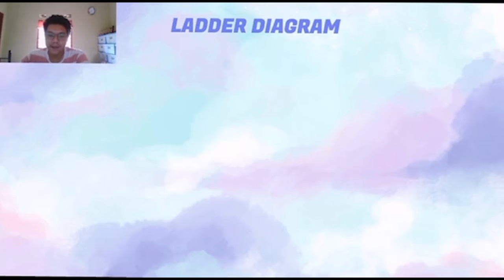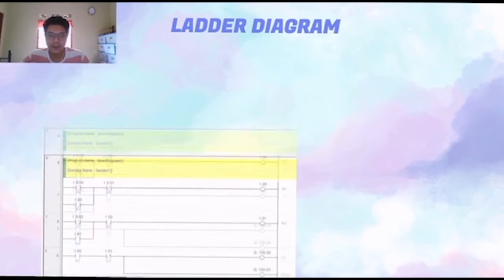Ladder diagram: commonly used to document industrial control logic systems, called ladder because they resemble a ladder with two vertical bus bars for power supply, left and right. The left side is 24 volts and the right side is 0 volts, with as many rungs, or horizontal lines, as needed to represent the control circuits.